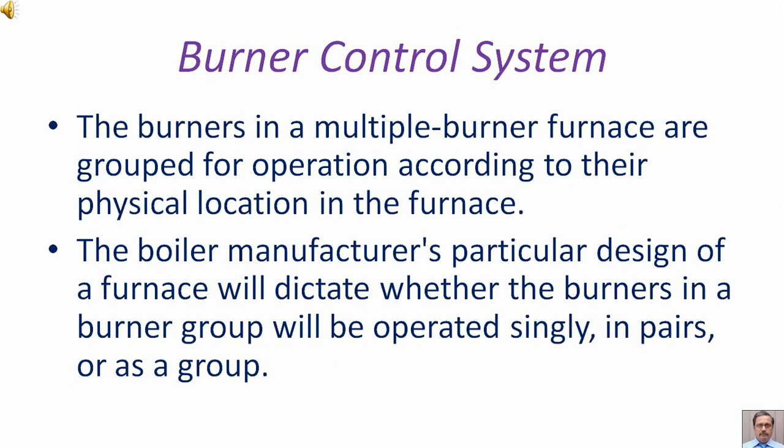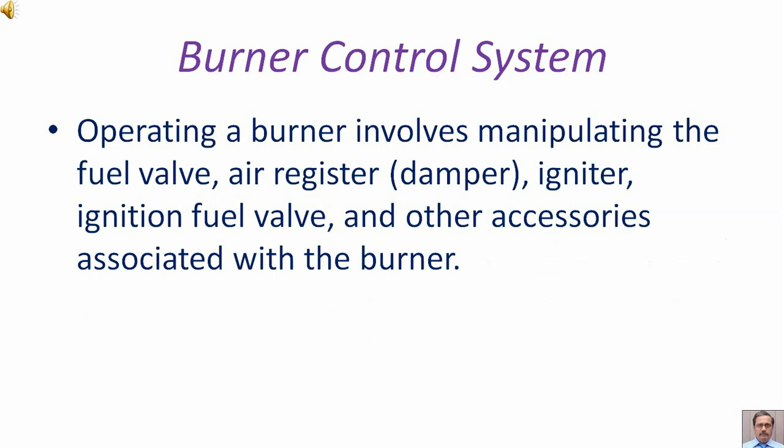The burners in a multiple burner furnace are grouped for operation according to their physical location in the furnace. The boiler manufacturer's particular design of a furnace will dictate whether the burners in a burner group will be operated singly, in pairs, or as a group. Operating a burner involves manipulating the fuel valve, air register, that is damper, igniter, ignition fuel valve, and other accessories associated with the burner.